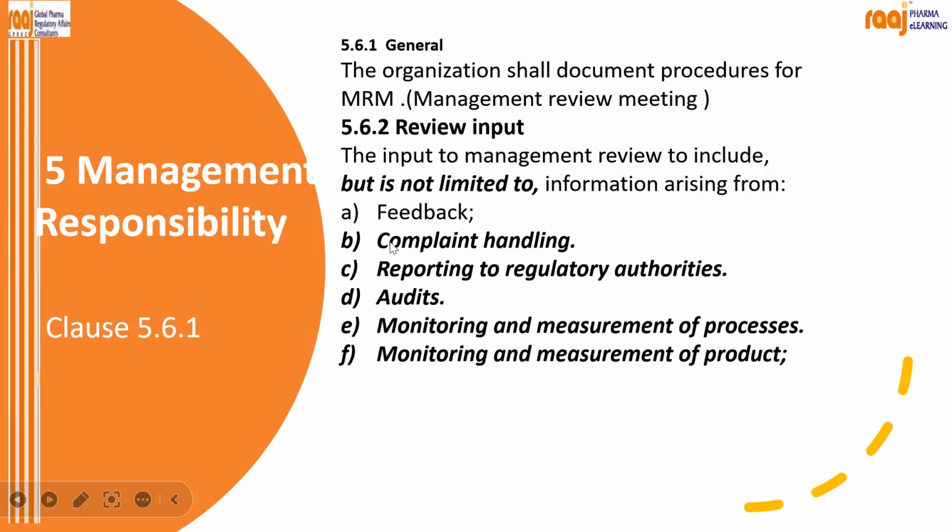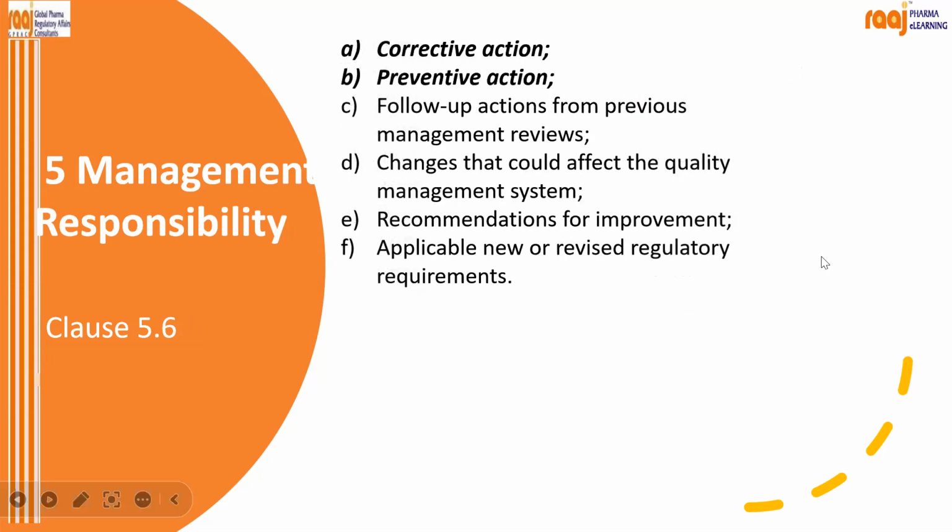Review input. We have to discuss feedback, complaint handling, reporting to regulatory authorities, audits, monitoring and measurement of process, monitoring and measurement of product. All these points come under review input. Then corrective action, preventive action, follow-up from previous management reviews, changes that could affect the quality management system, recommendation for improvement, applicable new or revised regulatory requirements. These are all the inputs.